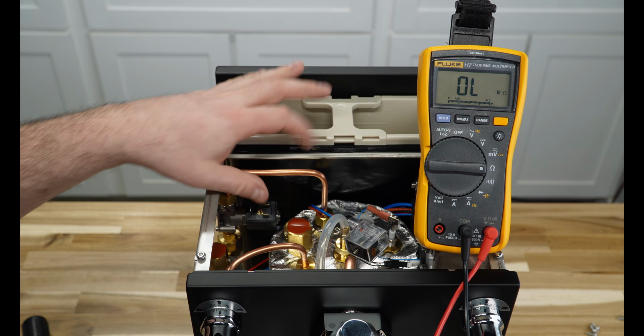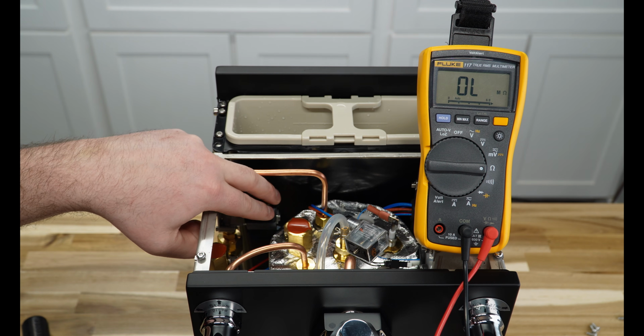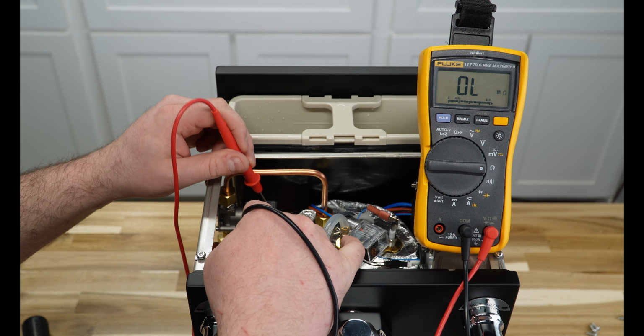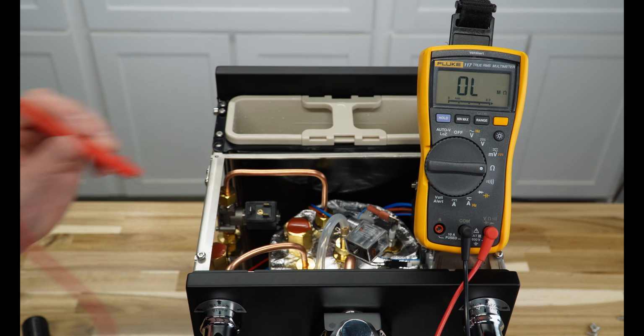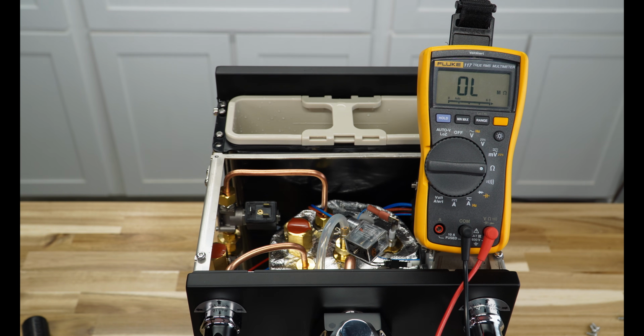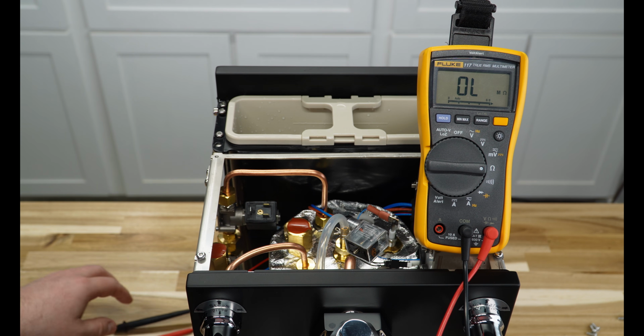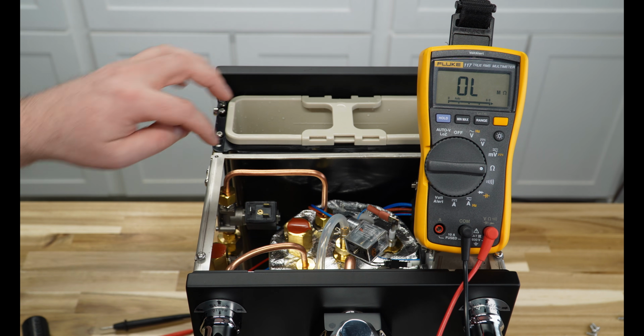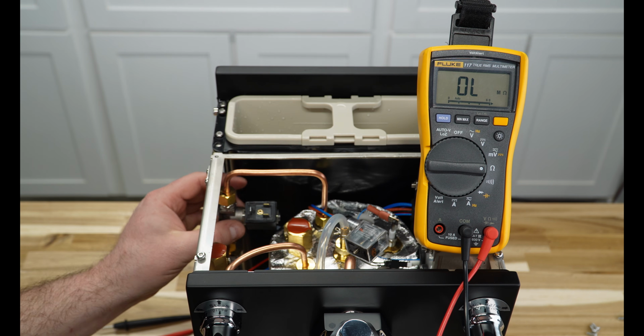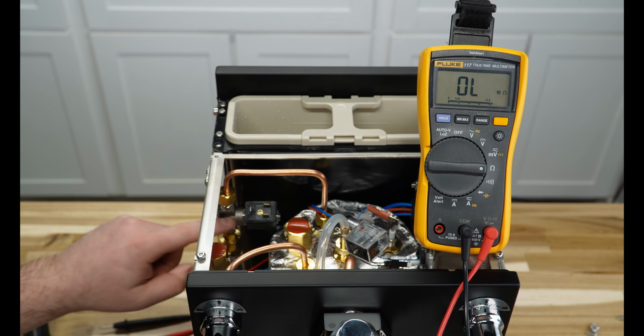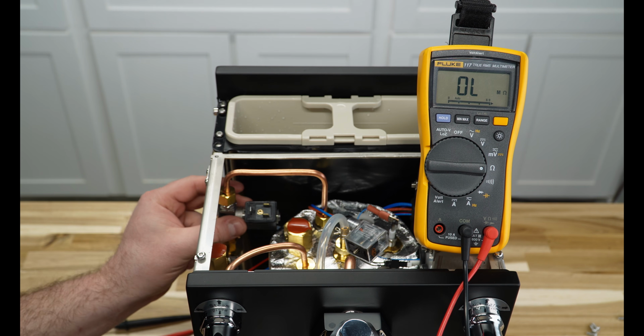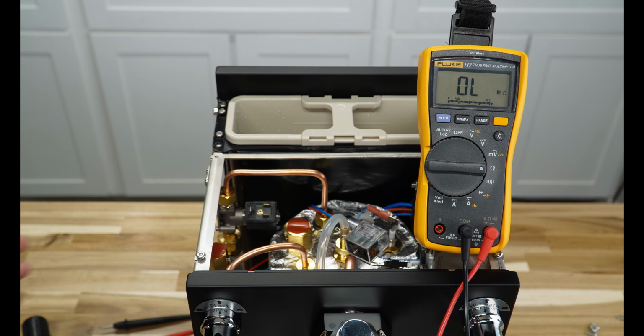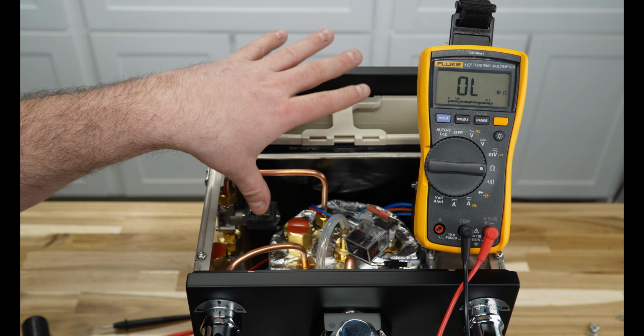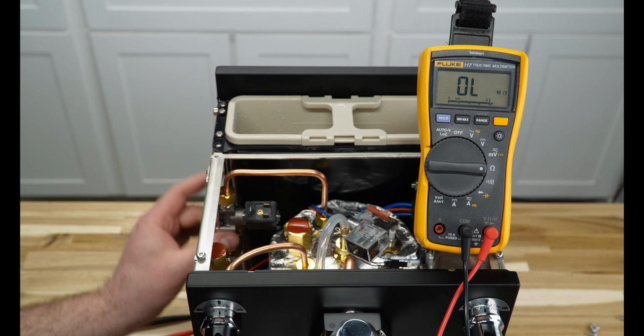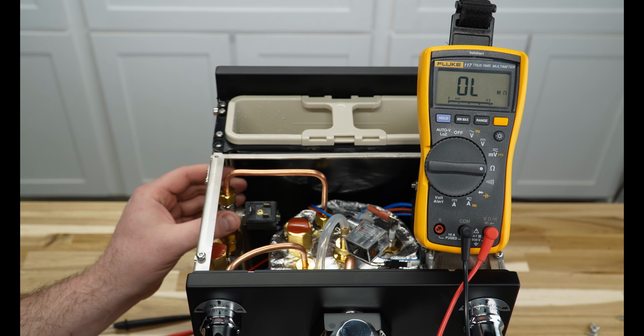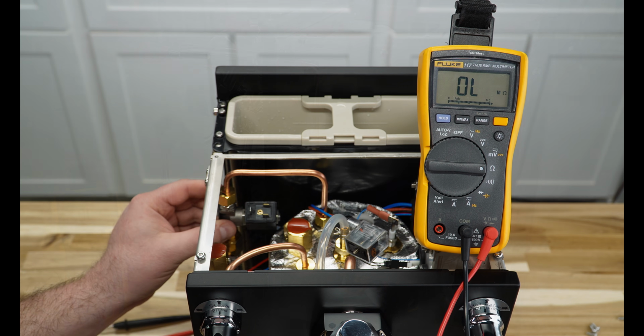And really all that is measuring is through that small inductive coil. Now, if you were to touch these two together and it said OL, open line, you would know that one of these is burned up. So that's the electrical way of checking this. This one is a little bit more difficult to get to, and I don't want to take it all apart. But if you needed to replace the plunger, sometimes, again, if you have that poor quality of water, your plunger will actually get stuck on the inside, and this whole assembly will need to be replaced. So it can be a little bit more difficult to troubleshoot, but you'll know if you're getting power and it's at least attempting to open and you're not getting water through, you're most likely going to need to deep dive into why that plunger isn't actuating.